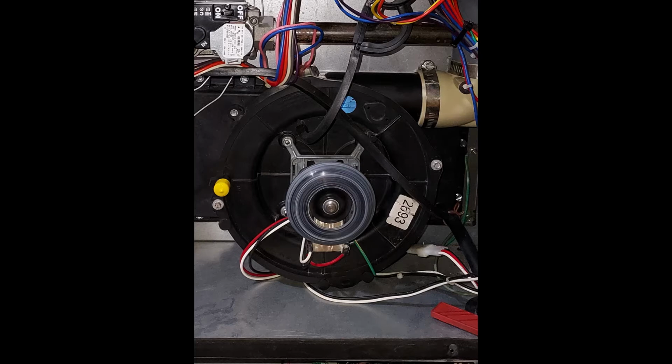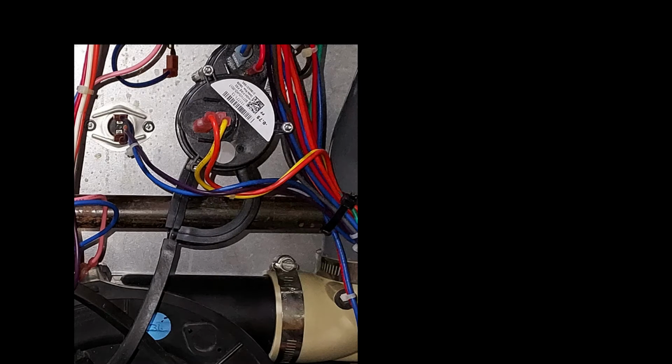It's connected to a hose that goes up to the pressure switch. And that pressure switch, when that inducer comes on, creates a vacuum through the hose, and the pressure switch closes and then sends a signal down to the furnace board, computer board, to go ahead and start the ignition process. So again, this is the very first thing that comes on, closes the pressure switch, which we're going to cover next. This is your pressure switch, and it is connected to the inducer motor via a hose.